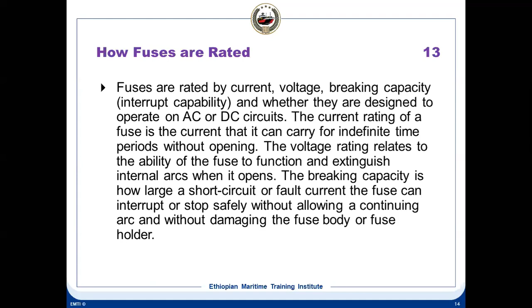The current rating of a fuse is a value expressed in amperes that represents the current the fuse will allow without opening. Voltage rating indicates the ability of the fuse to quickly extinguish the arc after the fuse element melts, and the maximum voltage the open fuse will block. So this is the difference between current and voltage rating. After the fuse element melts, you can get an arc because of inductive loads. So voltage rating indicates the ability of the fuse to quickly extinguish the arc.